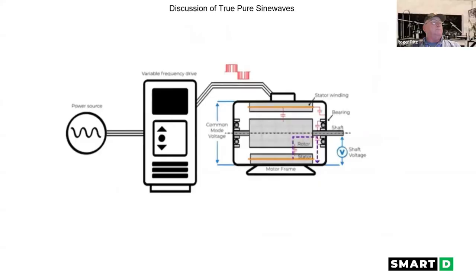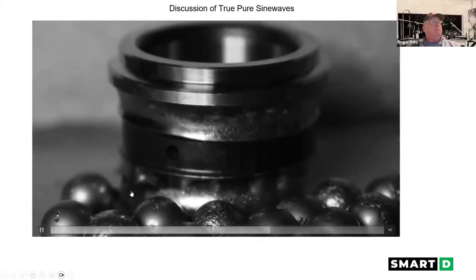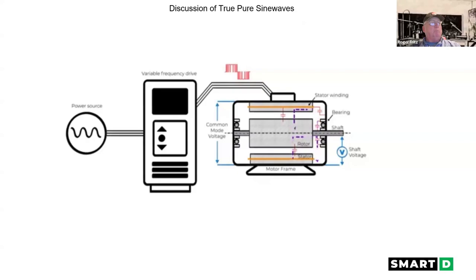dV/dt of the common mode voltage in the stator windings generates pulse currents flowing to the rotor. Part of this current flows between the inner race and the outer race of the bearings, causing heat in the lubricant. Common mode voltage generates an electric charge stored in the parasitic capacitance between the rotor and the stator. When this charge gets high enough, it breaks the dielectric insulation and is discharged through the insulation of the bearing. The capacitive discharge current can cause fretting of the bearing and raceways and produces temperatures high enough to melt the bearing steel and cause pitting. If the motor frame is poorly grounded and the motor is connected to a mechanical load that has a proper grounding, low impedance, the common mode current flows through the shaft reaching for the lower impedance.